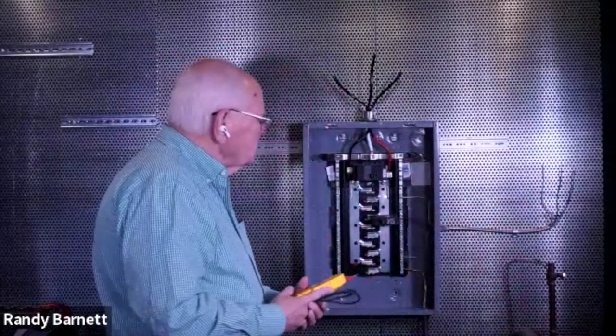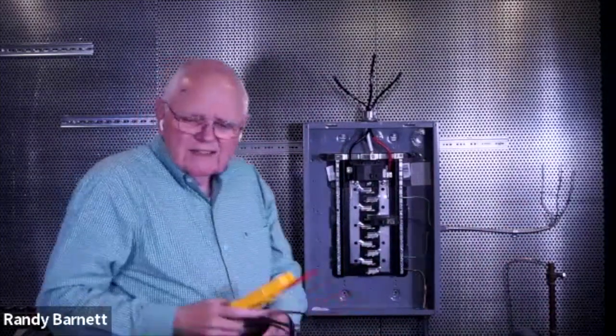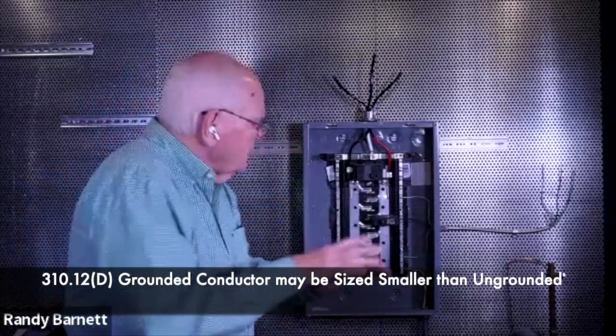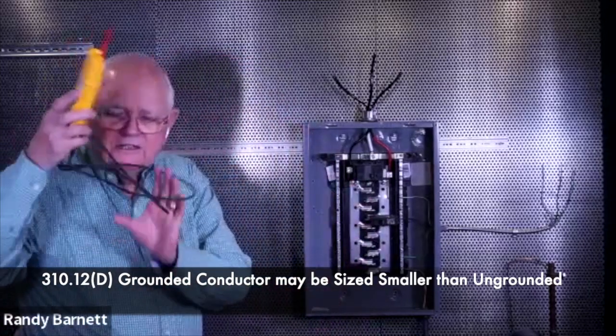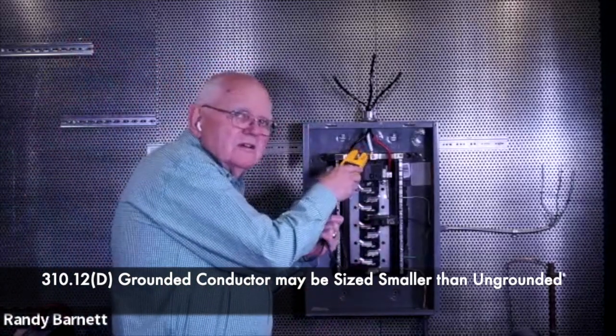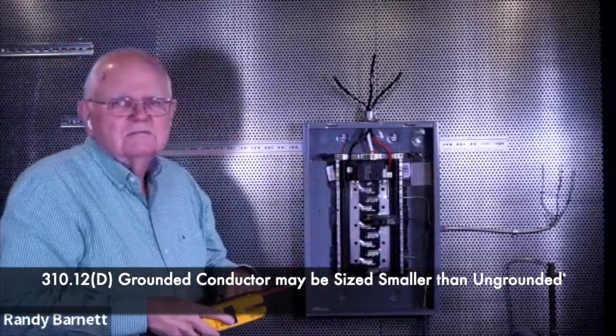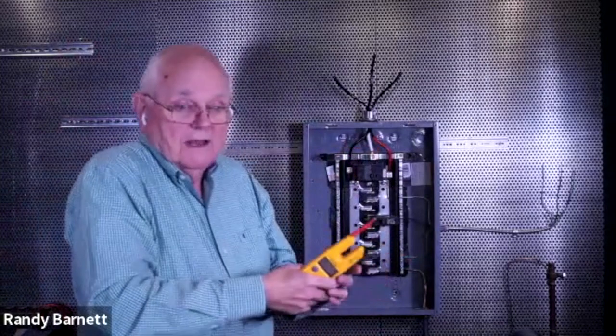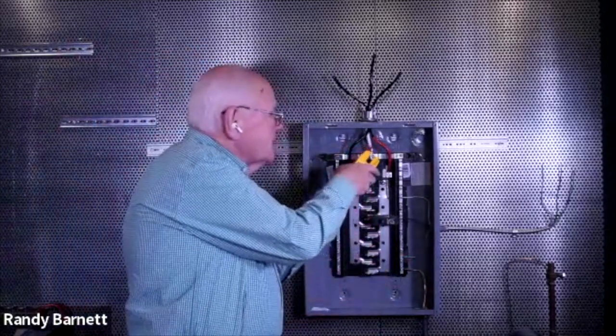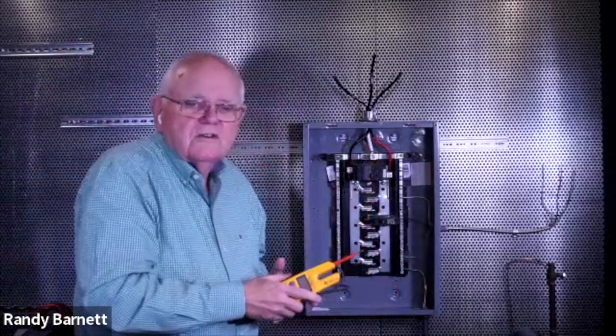Now, let's talk about how we size some of these conductors and maybe some of the issues we run into. If I take a look in my code book, for instance, I find that 310.12 is going to tell me that this grounded conductor can be smaller than the ungrounded conductors coming in. So it's permitted to be that, and a lot of people go, oh, that can't be. Yeah, it's permitted to do that. So I can make the neutral conductor right here smaller if I need to, but generally we don't do that. Generally, we make them the same size as the ungrounded conductor.